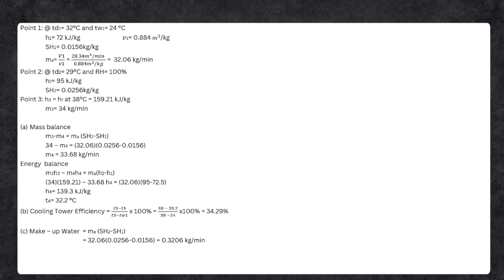So for letter B, cooling tower efficiency is equals to T3 minus T4 all over T3 minus TW1 or yung wet bulb temperature number 1 times 100% is equals to 38 minus 33.2 all over 38 minus 24 times 100%. Ang ating efficiency ng cooling tower is equals to 34.29%. So for the makeup water, ang formula ng makeup water is equals to MA multiplied by SH2 minus SH1. And by substitution, 32.06 kg per minute multiplied by 0.0256 kg per kilogram minus 0.0156 kg per kilogram, ang ating makeup water is equal sa 0.3206 kg per minute.